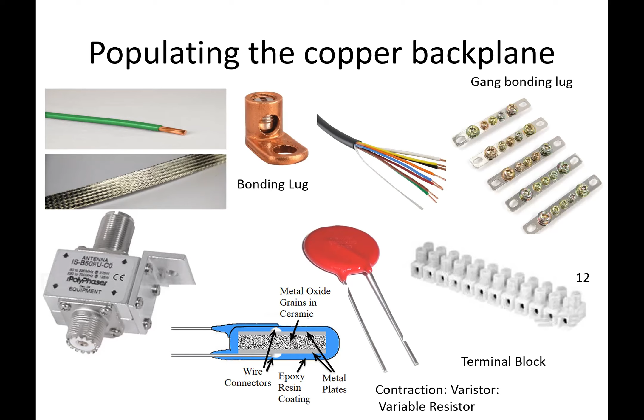Okay, polyphasers, or lightning protection for the coaxial feed lines. This slide depicts 4 different types of devices designed to protect coaxial feed lines coming into your shack. The upper left is what we use at the EOC, but there are others with different device ratings, wattages, and abilities. The one in the upper right corner is designed for DC to 2500 megahertz, 400 watts, and can discharge DC voltage up to 350 volts.